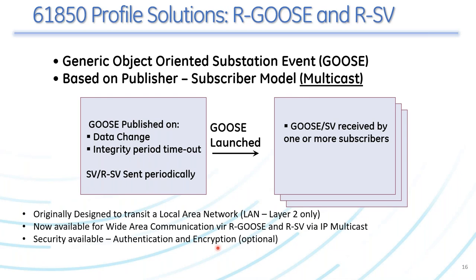The solutions for this are based on IEC 61850. There are now four profiles for this multicast messaging: the original one known as GOOSE — the Generic Object-Oriented Substation Event — which is a multicast model; and these have been enhanced in the most recent release of IEC 61850, which adds the concept of routable GOOSE and routable sampled values. These routable protocols use a routable IP multicast address, which allows one message to be sent via networking to many different locations. That's what I have on this section — Beth, I turn it back over to you.